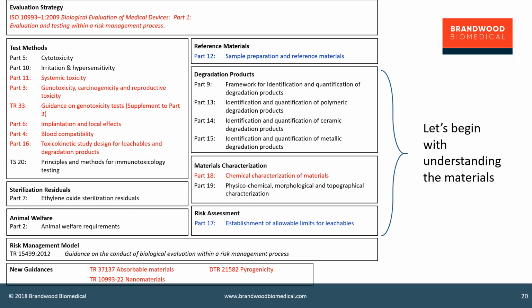There may be some low-level release of metallic ions and corrosion products, but if they are 3D printed surgical steels, 3D printed surgical titanium alloys, then you would not expect there to be much release at all. And then if you can show that through chemical characterization testing, you can make an argument that you do not need to proceed to biological testing because, in fact, there's no release.